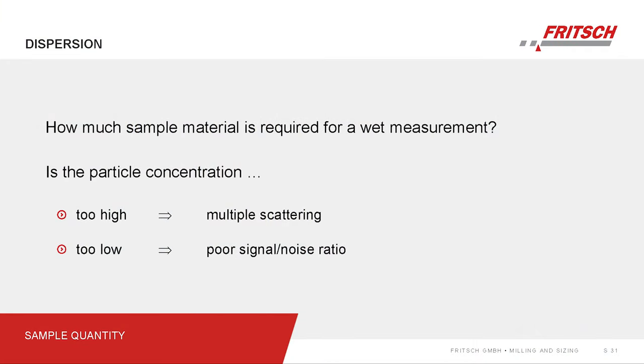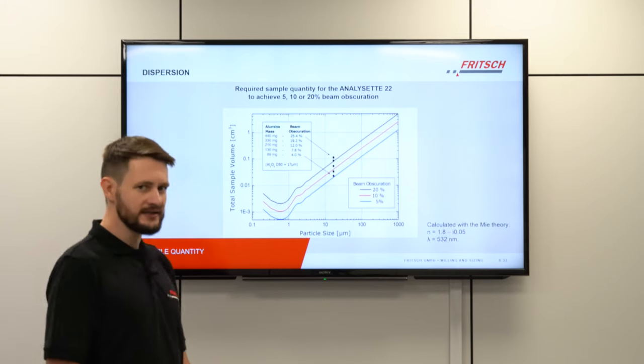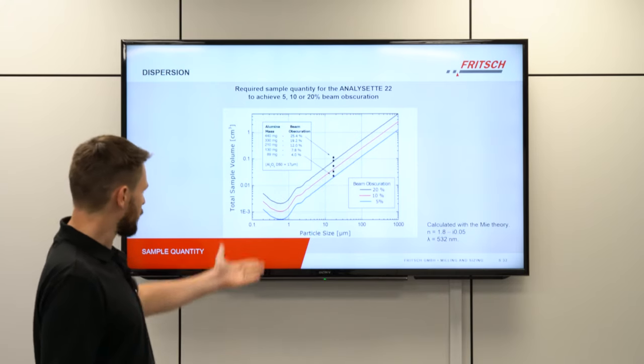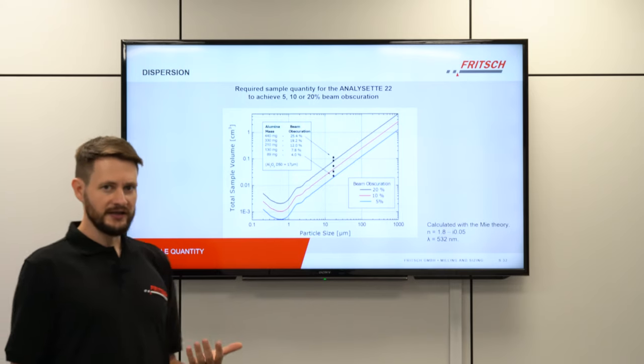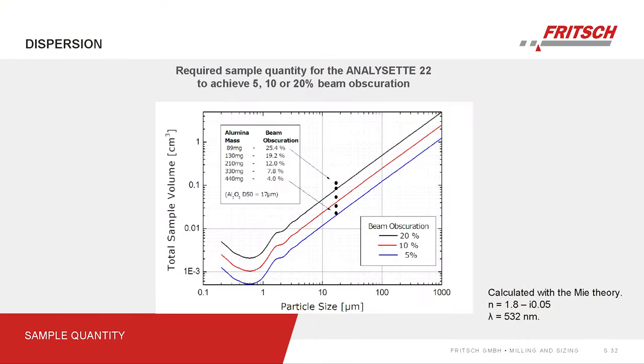The parameter we use to determine sample concentration in the wet dispersion is the so-called beam obscuration — the percentage of laser light that is diffracted away from its original path, which has a direct relation to sample volume in the dispersion. On this graph, total sample volume needed is shown as a function of particle size for three different beam obscuration values. Typically we look for a value somewhere in the range of 10 to 20 percent. Clearly, the amount of sample needed is much higher as particles become bigger.